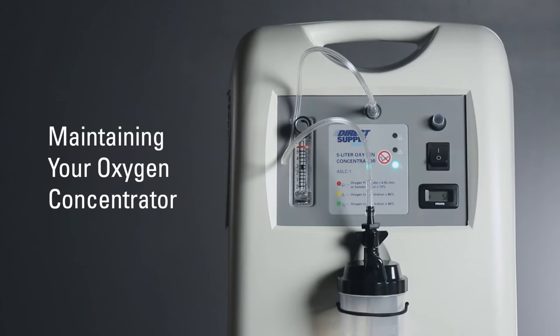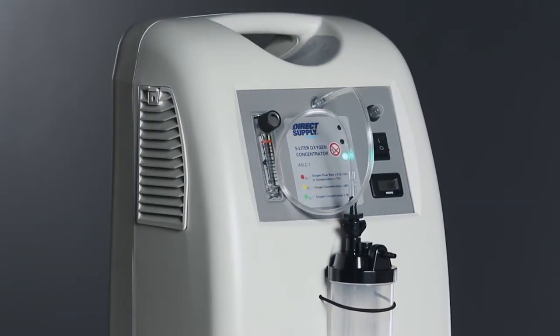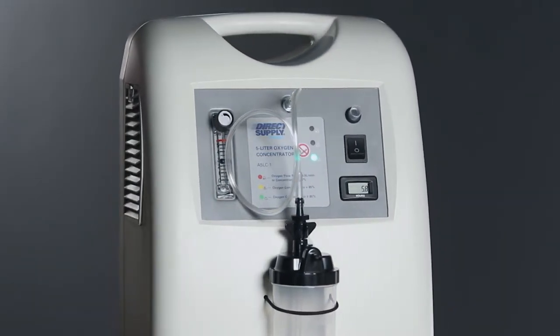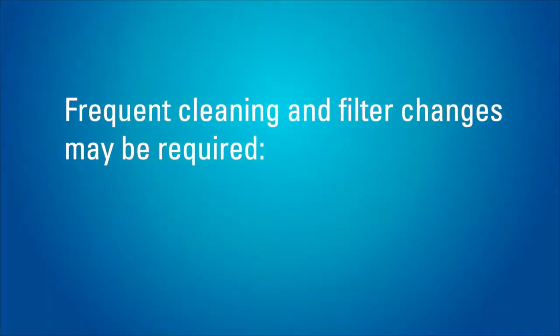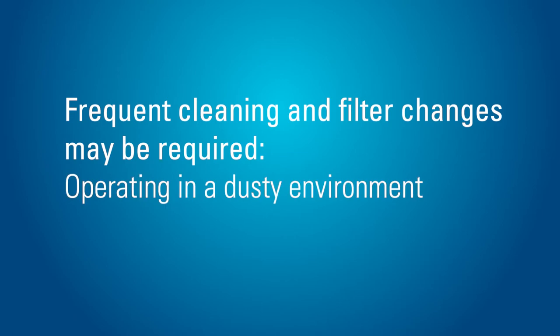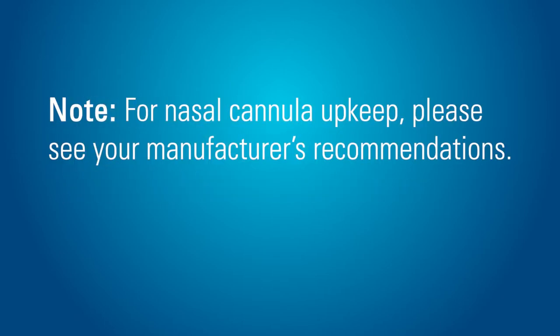When used in a clean environment, the concentrator typically requires no filter cleaning or changes for one year. More frequent cleaning and filter changes may be required if you are operating the concentrator in a dusty environment, you are operating the concentrator continuously, or your facility policy requires more frequent maintenance. Note, for nasal cannula upkeep, please see your manufacturer's recommendations.